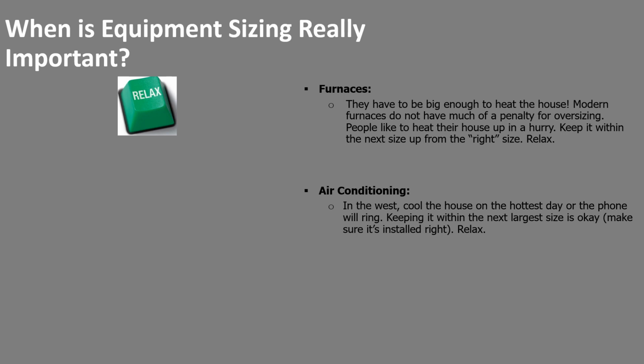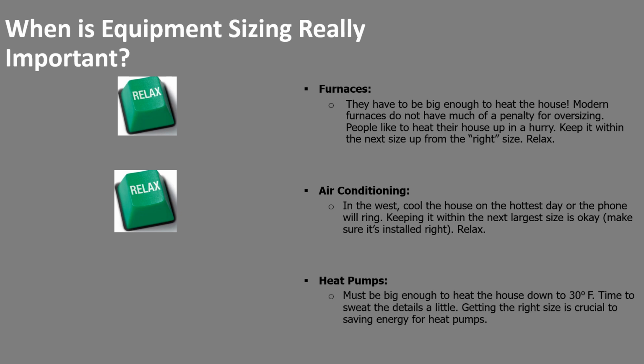Air conditioning, because we live west of the Rockies, it means that we're lucky enough not to have high humidity during the summertime months. What that does, it allows us to focus on the sensible capacity of the air conditioner and not the latent capacity, latent referring to the ability of the system to remove water vapor from the house. Heat pumps, they get a little more complicated. They have to be big enough to heat the house down to 30. We call that 30 degree the balance point. Time to sweat the details a little bit. And we have to spend a little more time on picking that heat pump.